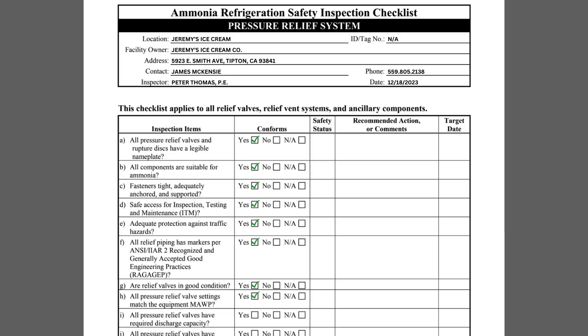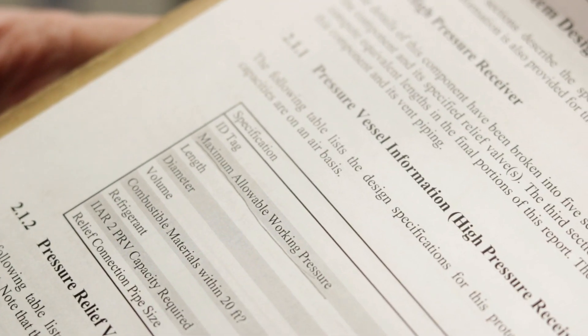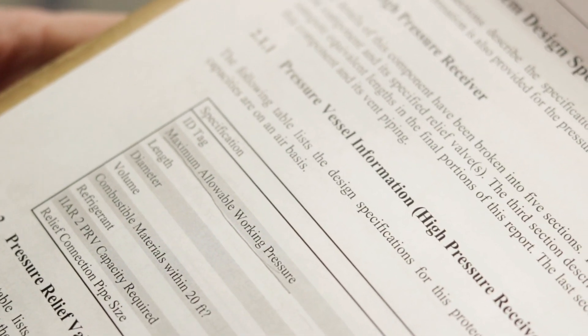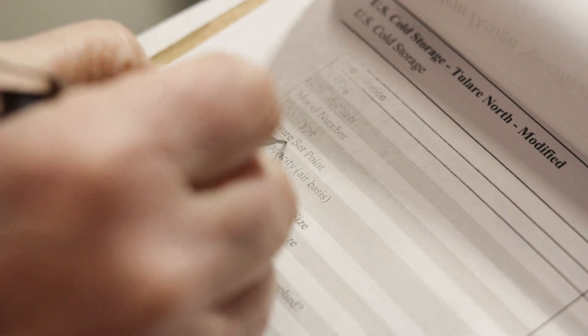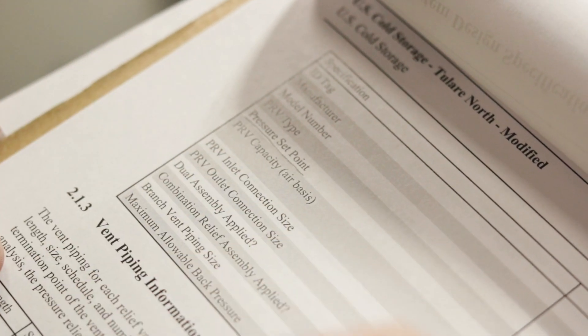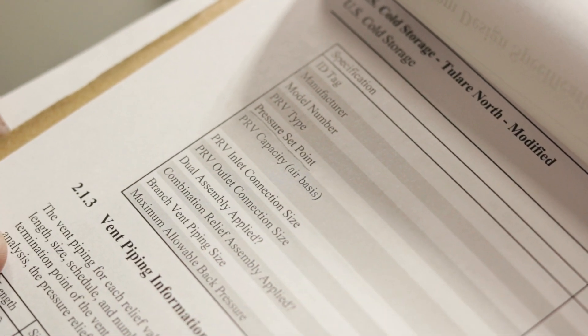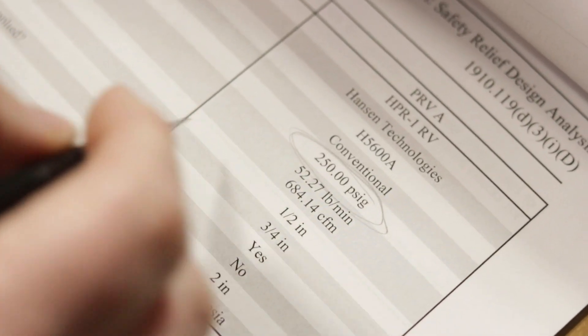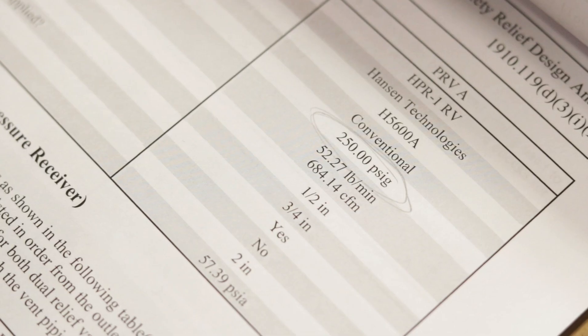Item H asks if pressure relief valve set pressure matches the maximum allowable working pressure, or MAWP, of the equipment that it protects. The relief valve must have a set pressure equal to or less than the equipment MAWP.